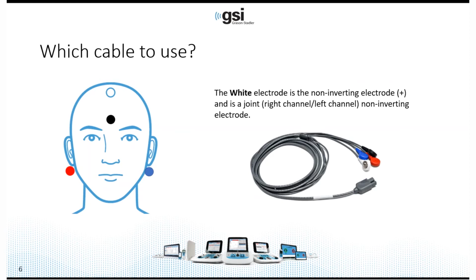The snap lead cable is all-in-one, and the white snap electrode is the non-inverting electrode, positive, and is a joint electrode for the right and the left ear non-inverting. So think of it as the jumper cable that's hardwired into this cable. So if you use this electrode, white is positive, high forehead, black is ground, red is right, blue is left. The benefit of this cable is you don't have to know where to plug the other end of the electrode lead into the patient cable because it's all in one and combined.